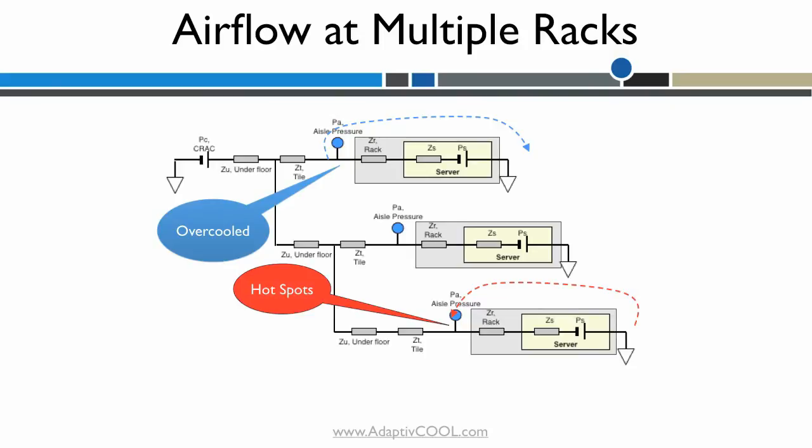To address a hot spot at the third rack requires increasing air flow by, say 20%, from 1000 CFM to 1200 CFM. This means the CRAC fan speed needs to be increased.